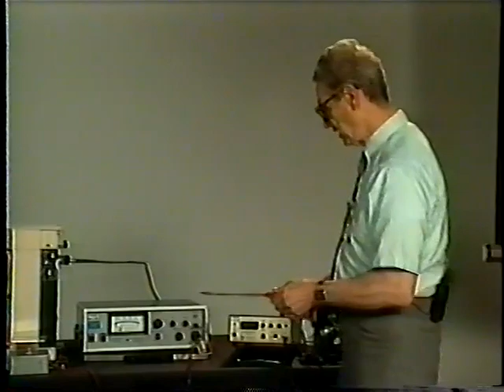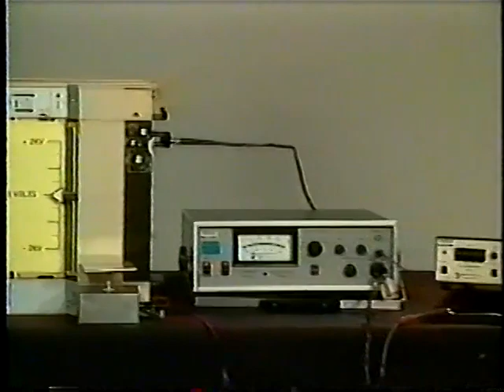We can show the calibration now by setting this power supply at 2 kV, then touch the electrometer head, and when I flip it on, it goes to minus 2 kV. If I turn the switch to plus, it goes to 2 kV plus, and if I remove the wand, that voltage stays there—that is the electrostatic voltage. Notice I can touch ground on the case and put my finger on the plate, grounding that voltage without any sensation of charge. This is how we calibrate the system, and we have a scale here that we can change to plus or minus 200 volts.